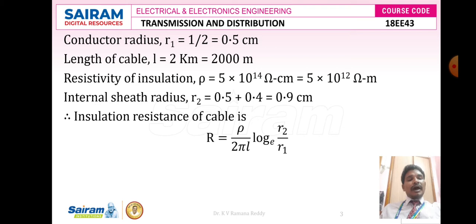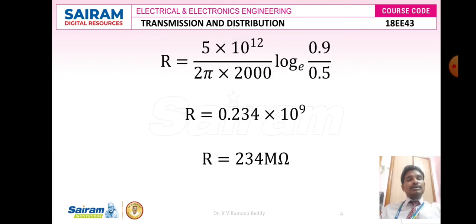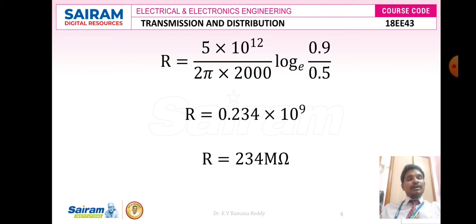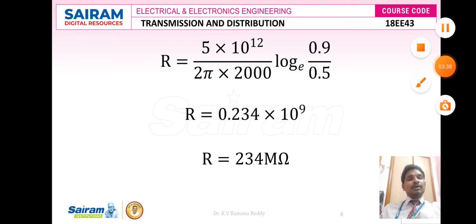Substituting the values: ρ = 5 × 10^12, l = 2000, r2 = 0.9, r1 = 0.5. After simplification, the insulation resistance R = 0.234 × 10^9 ohms, which in engineering notation is R = 234 × 10^6 ohms, that is 234 mega ohms.